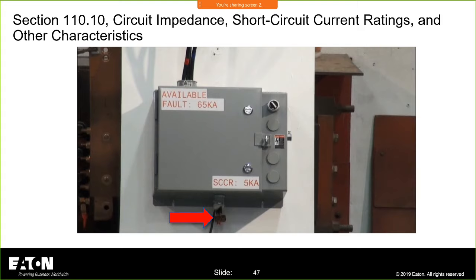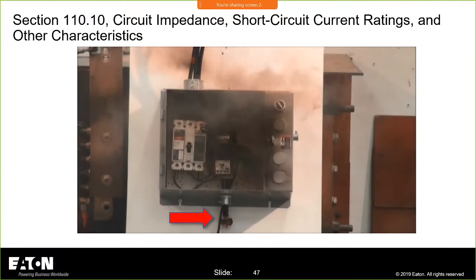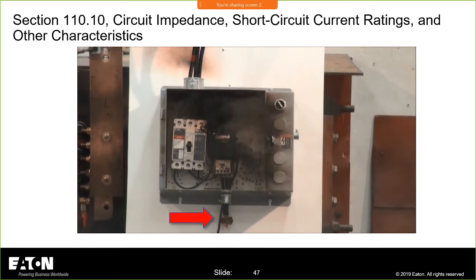So this is, again, 5K equipment. That door on that one actually flew about 20 feet across the floor. And just to coach this a little bit, this is misapplied equipment. This is a 5,000 amp short circuit current rating, and I'm hitting it with well above 5,000 amps of current flowing through it. And what you're seeing is, as Dan Neeser says, an unintended rapid disassembly in the field. You let the smoke out because it's misapplied product.